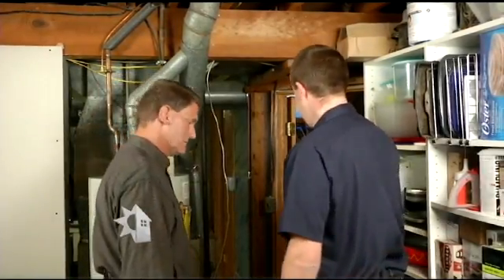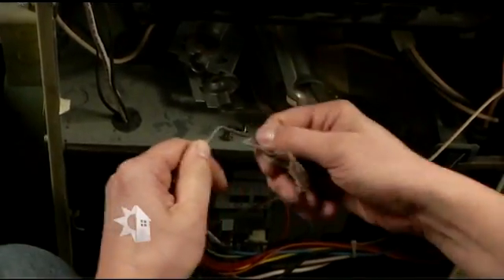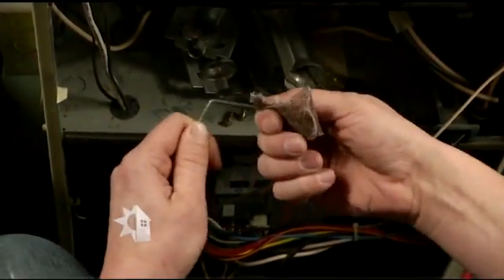Okay, can you show us what you take a look at when you go through the process? So Jacob, what are you looking for when you open this up? What's the first thing you're trying to identify? We're trying to make sure that there's nothing abnormal going on with the furnace. We check the igniter. We also check the flame sensor, which I have right here. We also check the burners, make sure they're clean. They'll cross-light correctly, because if they don't, then it'll cause an abnormal operation as well.